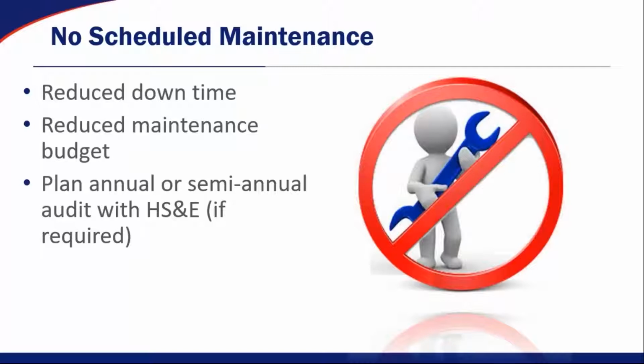But one thing that we do recommend, even though you don't have maintenance on a Phoenix product, we do plan annual or semi-annual audits with your health and safety group if required, again, just to go into the Phoenix system, manage everything on the network, make sure all the devices are communicating. And if you did have situations where something like a sash sensor on a fume hood broke, you could definitely look into that and fix it before it becomes a real problem. But the products themselves do not require ongoing maintenance.